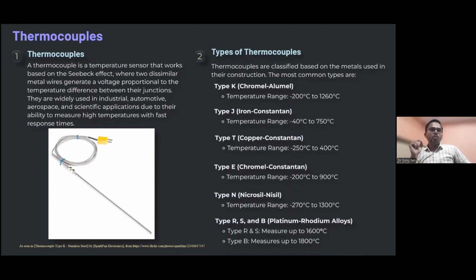After thermistor, one more important temperature sensor is the thermocouple, one of the most widely used temperature sensors across industries, from aerospace to EVs to food processing units. These small yet powerful sensors help us measure extreme temperature with remarkable accuracy. A thermocouple is a temperature sensor that operates based on the Seebeck effect. Its working principle is based on this effect, which states that when two dissimilar metals are joined at two junctions and exposed to different temperatures, a voltage is generated.